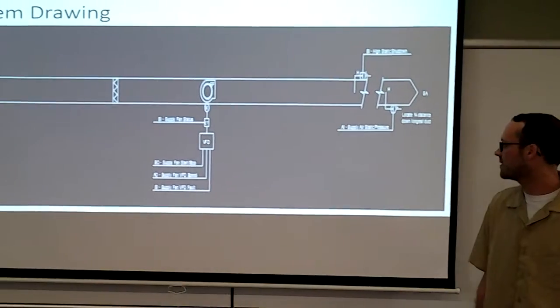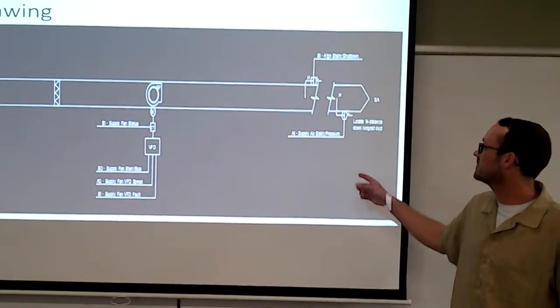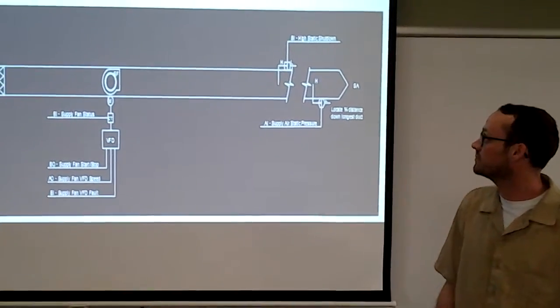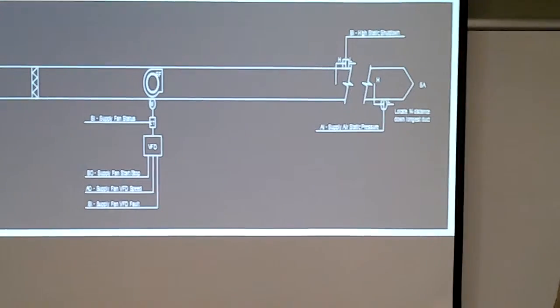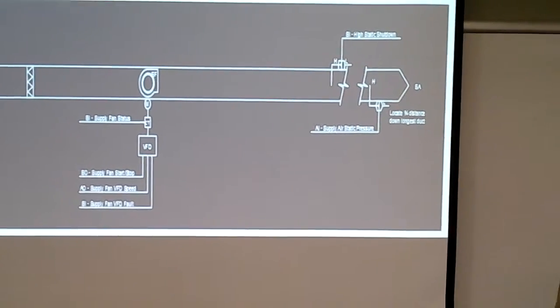We have our supply air duct static pressure sensor and then we have a high static shutdown sensor also and that's in the air handler unit. The static pressure sensor is three fourths of the way down the main duct.